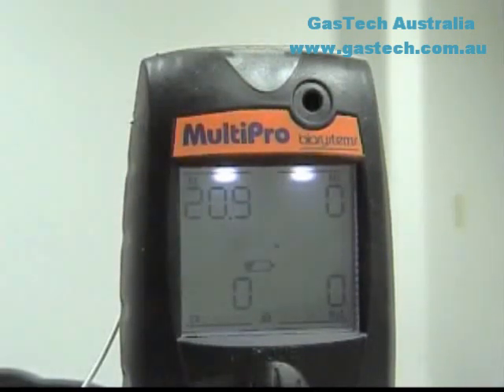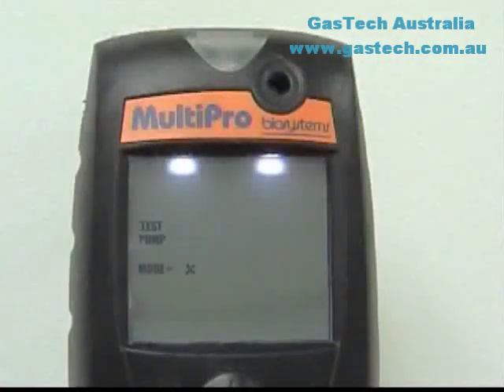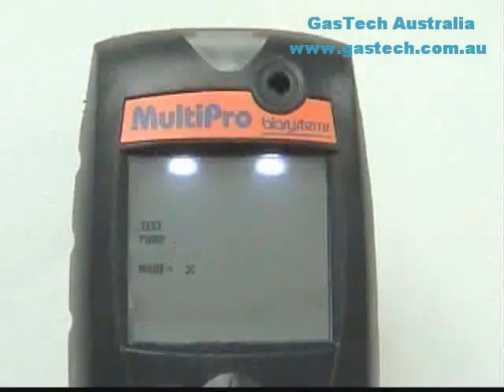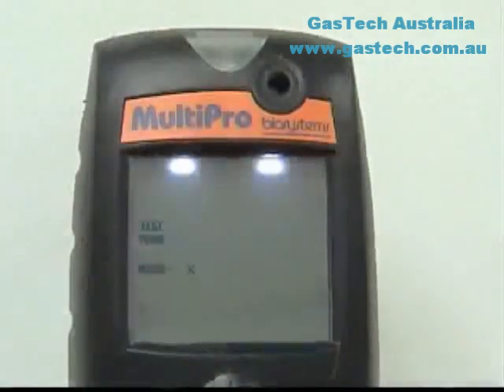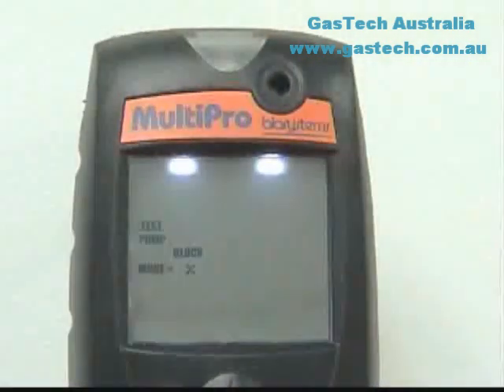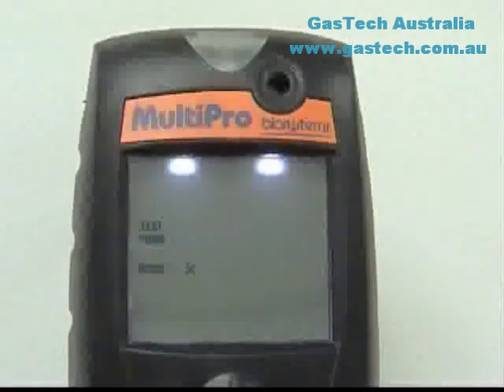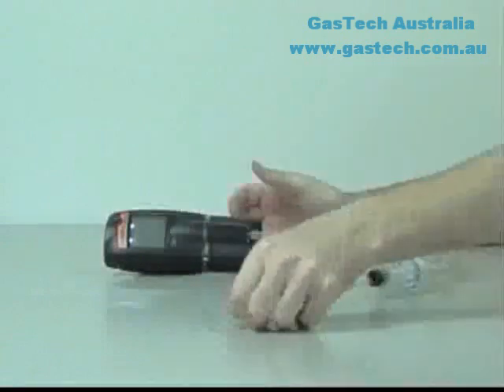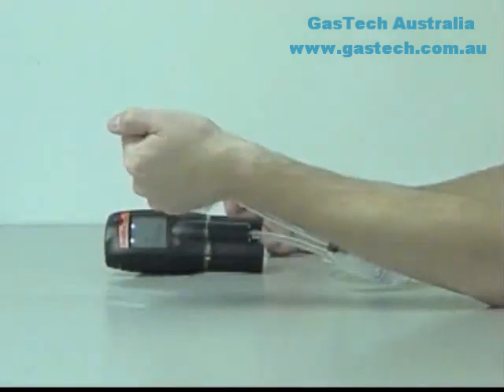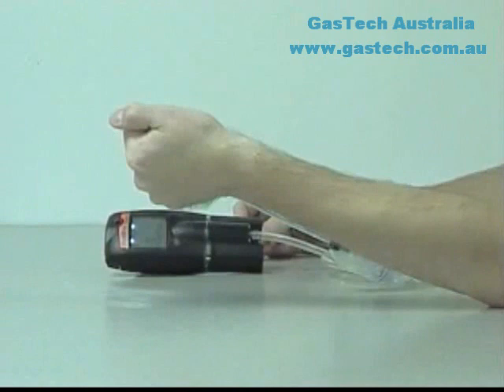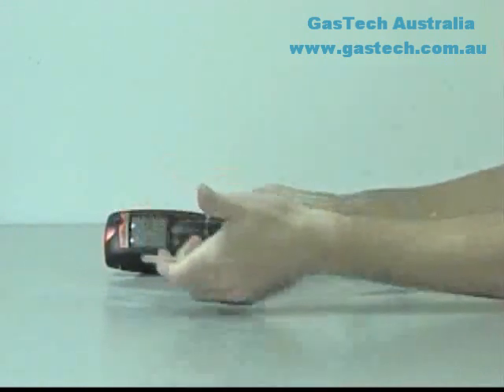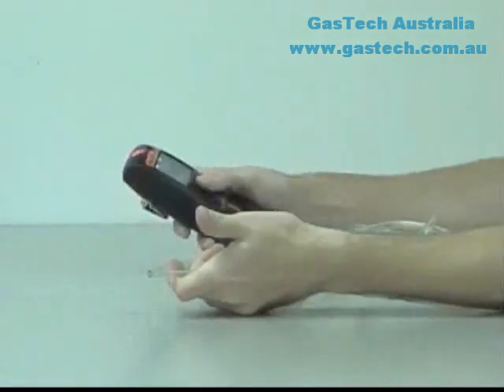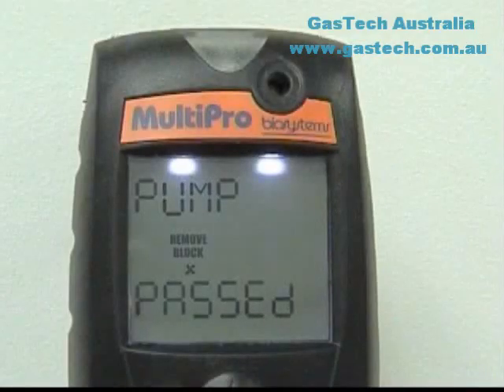If the pump is attached to the Multipro when the instrument is turned on, the pump will be activated and the sample draw assembly will be tested for leakage. The Multipro will instruct you to block the sample draw probe, which must be attached to the inlet port on the pump during use. Block the pump inlet by placing a finger over the end of the sample probe assembly. Once the instrument recognizes that the sample has been blocked, it will instruct you to remove the blockage. Once the blockage is removed, the instrument will proceed to the current gas reading screen.